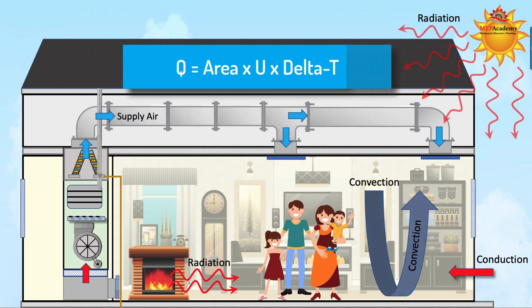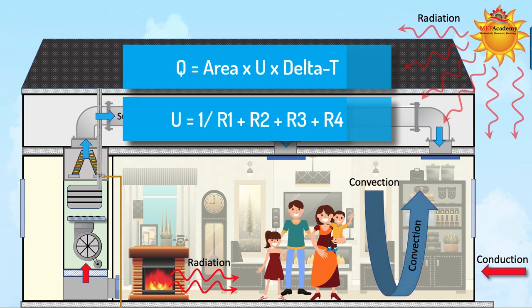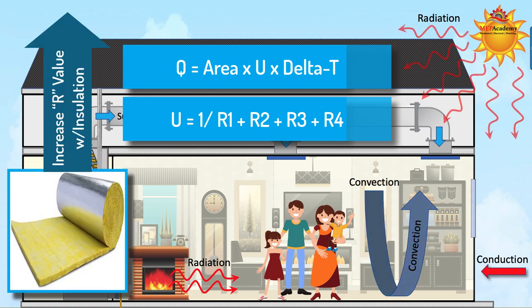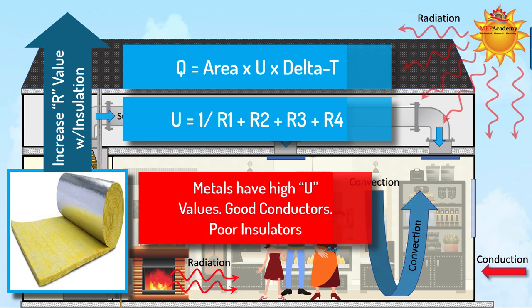The U-value is the inverse of the total resistance of the wall or roof assembly. The higher the R-value, the less the rate of heat transfer. This is how insulation reduces the heat transfer rate, while metals are highly conductive materials and easily move heat through them.